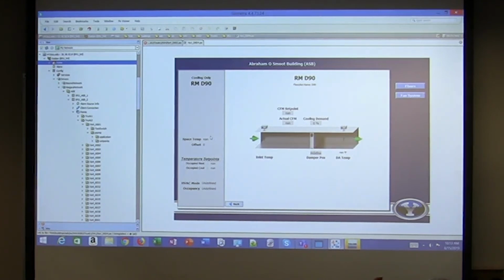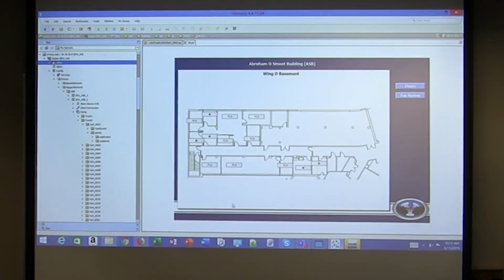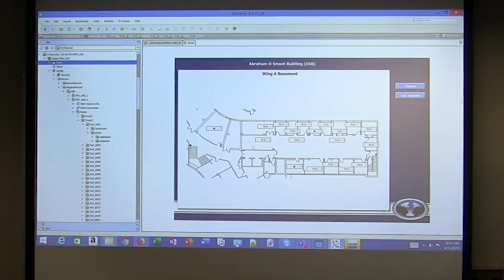If the stat was just missing, it would normally be like a 32 or a 99, depending on what controller it might be looking at. So this one doesn't seem to be giving us any data at all, but it doesn't show that it's yellow or anything, so we're not sure if we're really seeing good stuff or not. Okay? Looks like we got two that are still not communicating, the rest look like they're doing their thing. Okay.